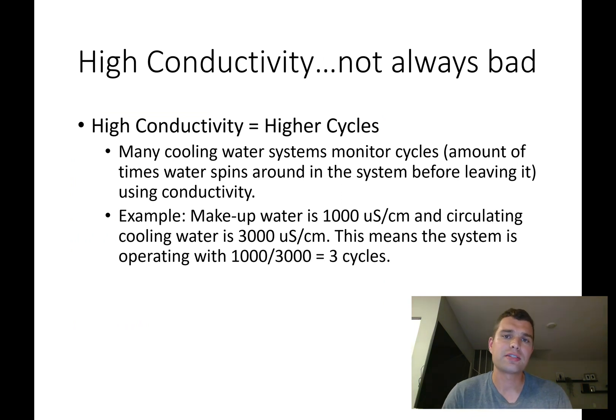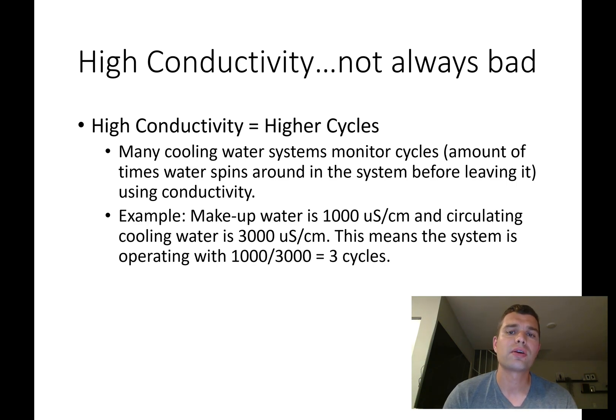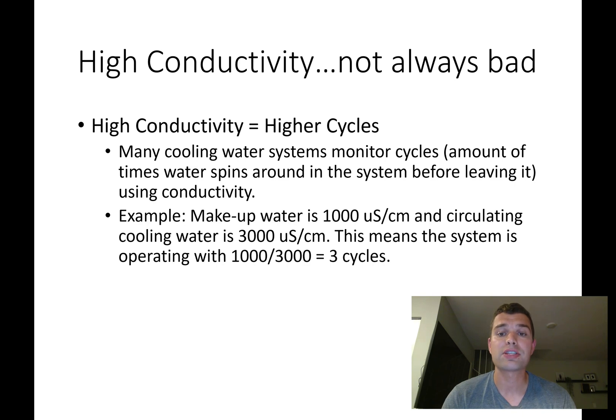High conductivity is not always bad — it's not the same as hardness. Typically, high conductivity means higher cycles of concentration in your cooling water system. Cooling water systems monitor cycles, which is how many times water circulates before leaving through evaporation or blowdown, and conductivity is used to measure that. For example, if your makeup water is 1,000 micro Siemens per centimeter and your circulating cooling water is at 3,000 micro Siemens per centimeter, the system is operating at three cycles.